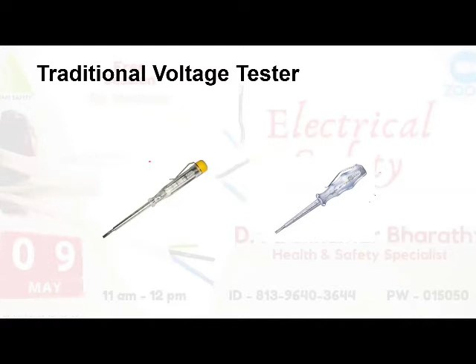Always try to avoid using it in industry. If you are using it at home, okay, fine, for single phase 220 voltage it is okay, but not for our industrial application. Don't use the traditional voltage tester, because it has a neon lamp inside and a resistor, and if you touch the backside it will give an indication. But it will even give an indication for leakage current. More than 70 volt AC, the tester will glow.